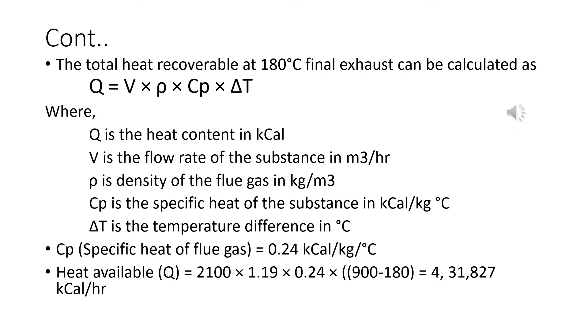Total heat recoverable at 180 degrees Celsius final exhaust can be calculated as Q = V × ρ × Cp × ΔT, where Q is the heat content in kilocalories, V is the flow rate of the substance, ρ (rho) is the density of the flue gas — a constant value of 1.19.